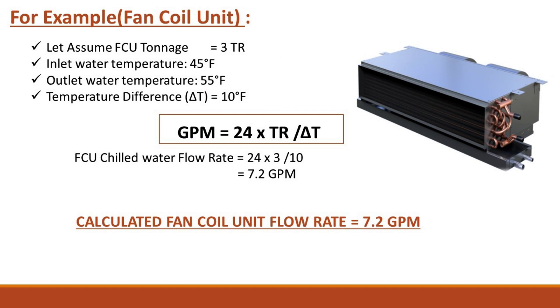For example, consider a fan coil unit. Assume the FCU tonnage is 3 TR, with an inlet water temperature of 45°F and an outlet water temperature of 55°F, giving a temperature difference ΔT of 10°F. Applying the formula: GPM = 24 × TR / ΔT = 24 × 3 / 10. The calculated fan coil unit chilled water flow rate is 7.2 GPM.